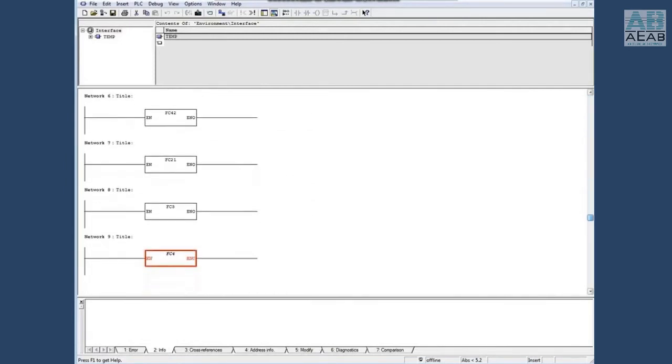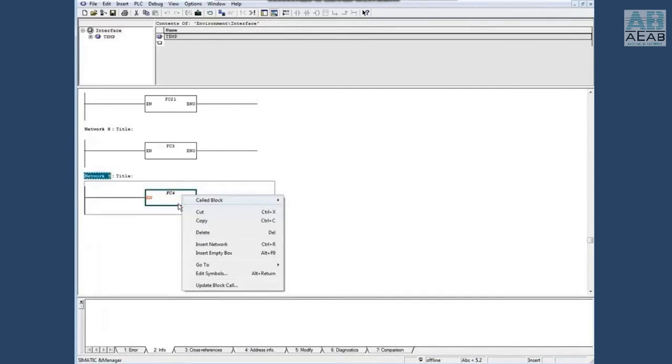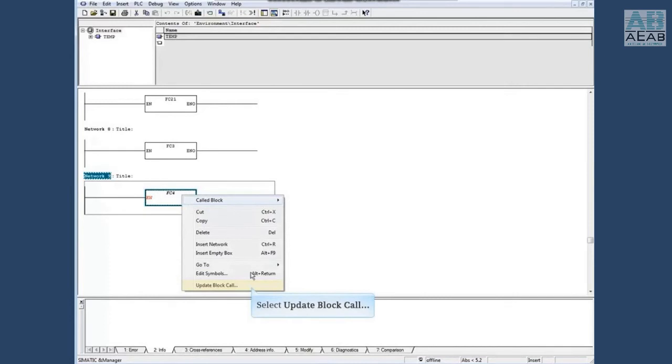Scroll down the block to find that the FC4 block is red. The pop-up note tells us that the interface was changed. Right-click the block and choose update block call. This option only shows when there is an interface conflict of the block.